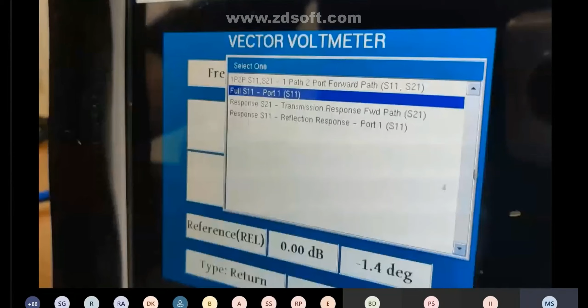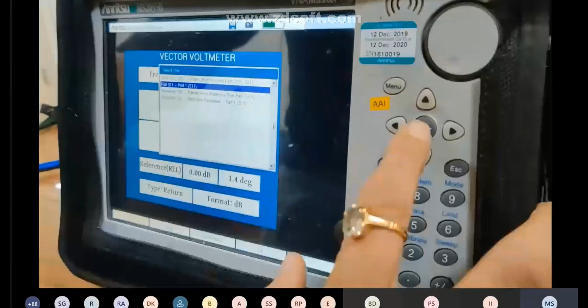Now we have to start. You have to choose which type of calibration you want to do. From here, we will choose S11, that is single port calibration, because we will not be using the second port in our objective, so here we will select single port.